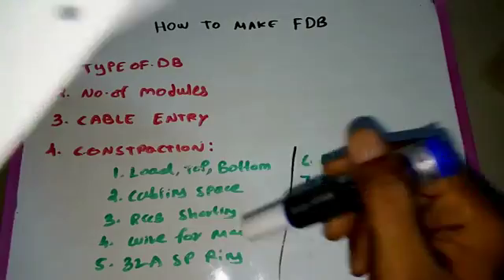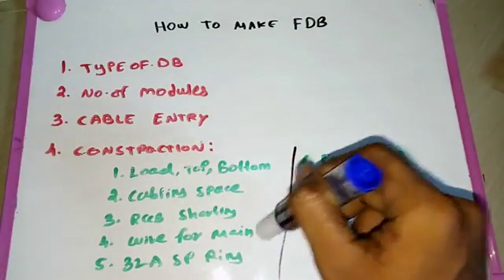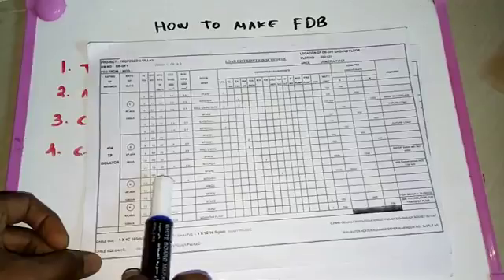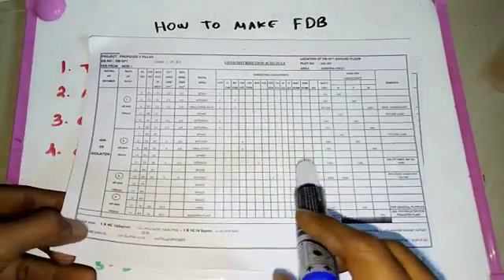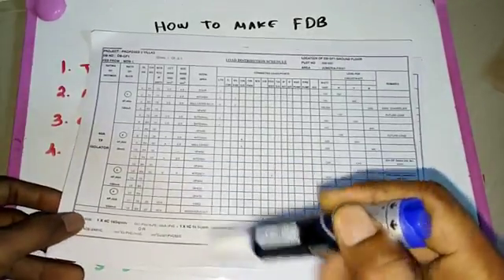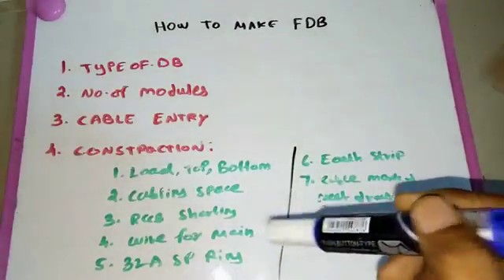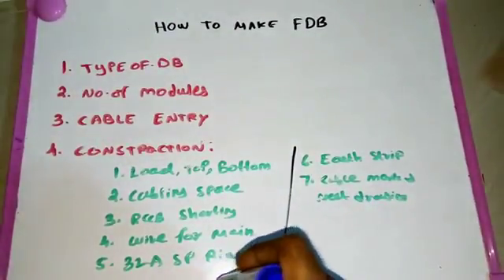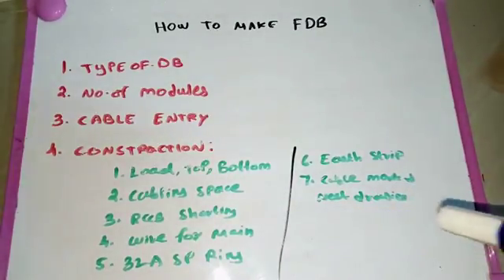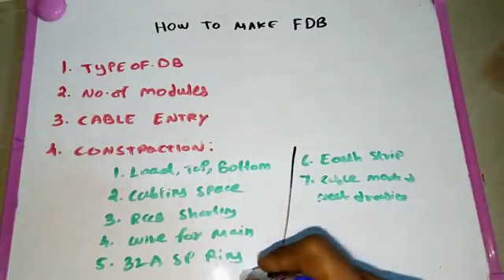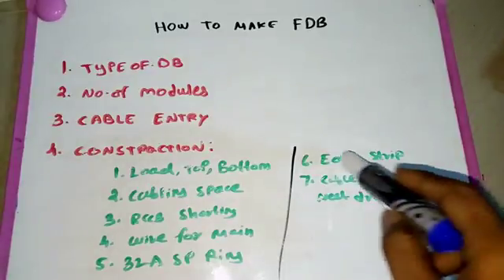For a 32-ampere breaker, we need to provide a ring circuit — that means two neutral points must be provided for the 32-ampere ring circuits. If it is already mentioned in the load schedule, we need to provide the ring circuit with extra neutral links accordingly.